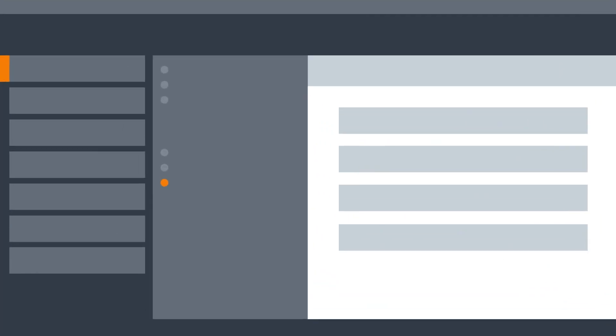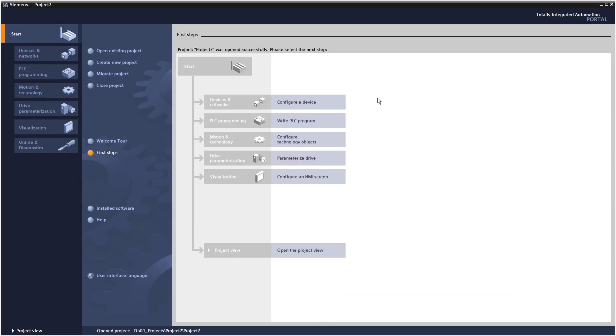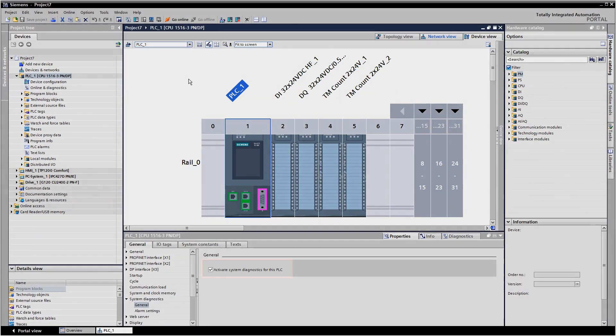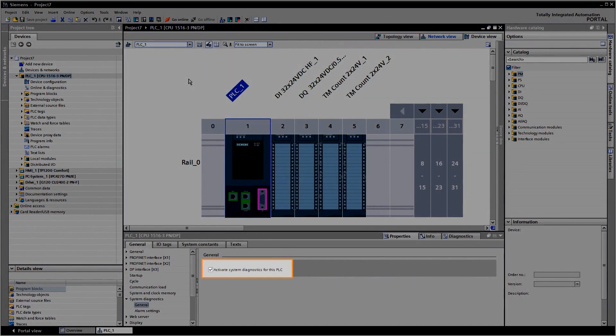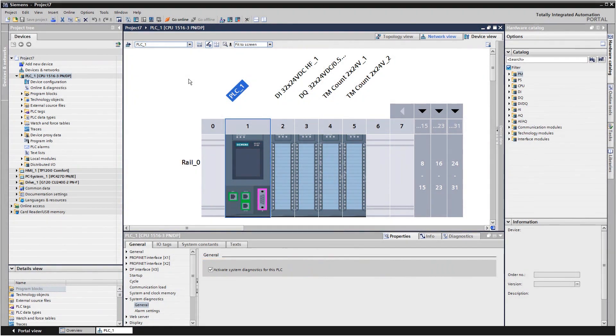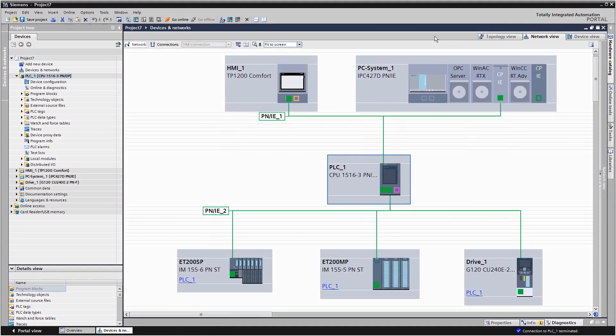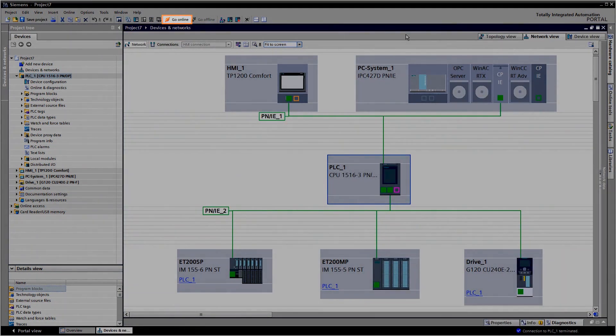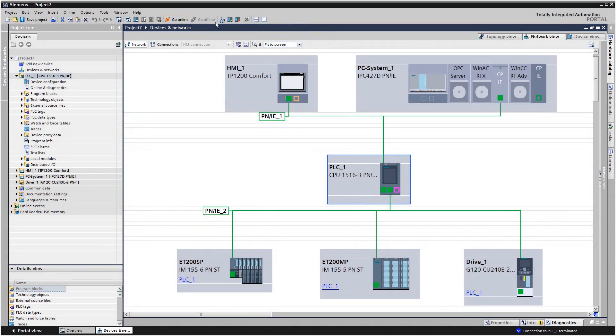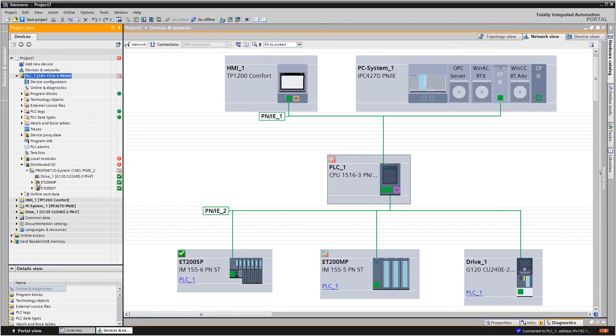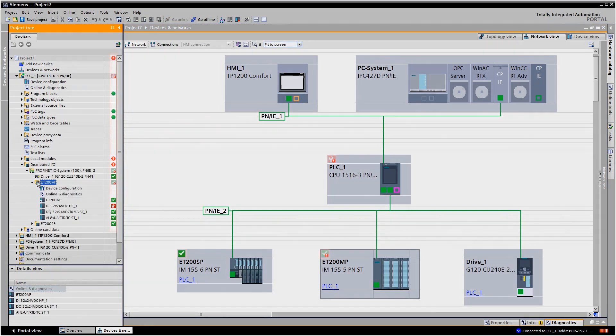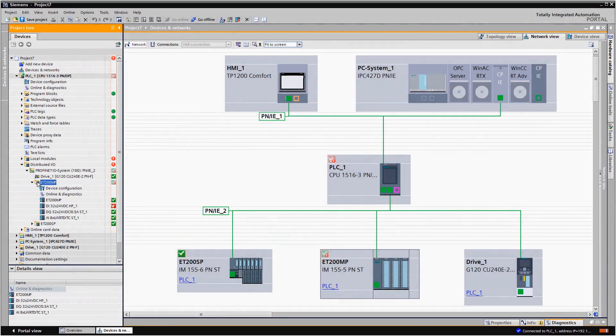How is that done in the TIA Portal? System diagnostics are activated as standard for controllers from the SIMATIC S7-1500 family. In order to view diagnostics information via the TIA Portal, you must set up an online connection to the controller. The symbols in the project navigation and the network view give you an initial overview of the status of your devices.